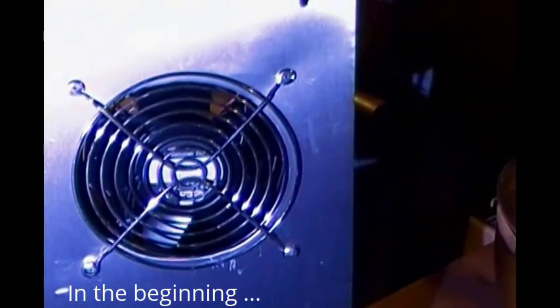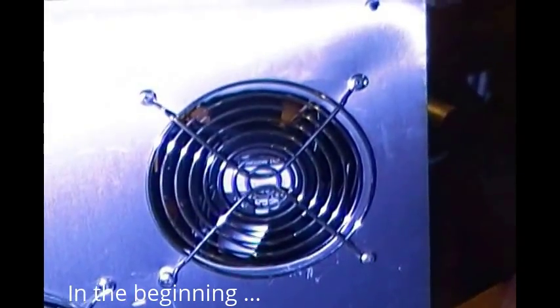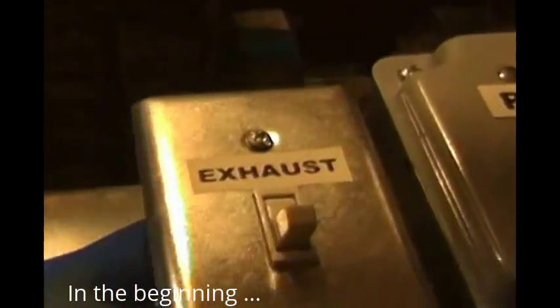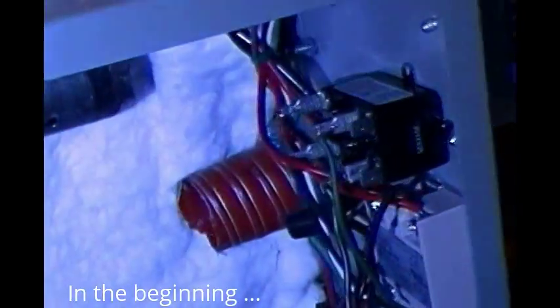It recognizes the power is now off. At that point, it kicks on two 85 cubic foot per minute muffin fans, which blow outside air in through here, across and through the heat exchanger copper tubing, and out the top, hitting a little flap. There are holes underneath, so hot air starts blowing out. This cools it down more rapidly than if it just used the air getting sucked through the heat exchanger alone. The heat exchanger is still sucking air through because of the exhaust suction, but it's cooled down vastly because of the extra air flowing through the unit.